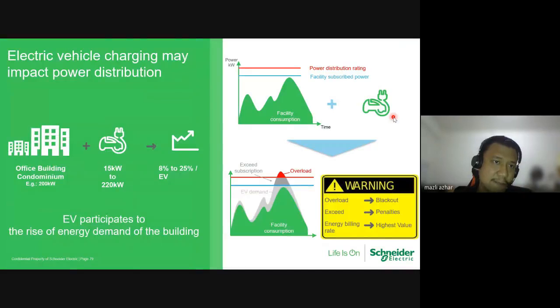Next, we have a load management system. Okay, compared to the cloud, this is another thing. Let's say you have an office building. It requires 15 to 220 kilowatts for a lot of chargers, which increases the demand by 8 to 25%. Okay, normally EV charging causes the rise of energy demand. Okay, what will happen when you exceed the load? You will have blackouts. You will get penalties from TNB because you exceed the monthly subscription power that you have subscribed with TNB, and you will have higher energy billing rates. Okay, this is what I call a waste of energy. Why? Because you are wasting a lot of energy to charge the car without using any smart system to handle it.